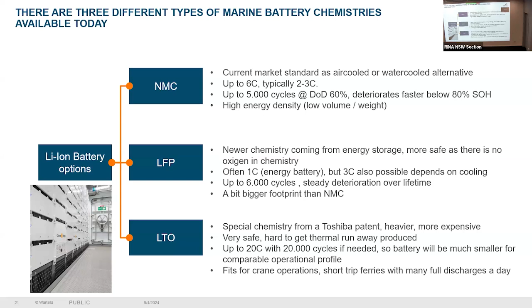Now, in this slide we will understand the terminology: when we say modules, when we say cells, when we say rack, what does it mean? A marine battery rack consists of cells, modules, packs, or strings. Cells are either flat or cylindrical. A module has the cells inside, packed in a way to avoid thermal runaway. Each module has certain current and voltage. It's not that one piece gives you the voltage you desire. It's all connected in series to reach the required voltage, and it can also be connected in parallel.